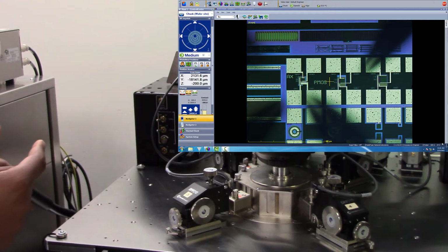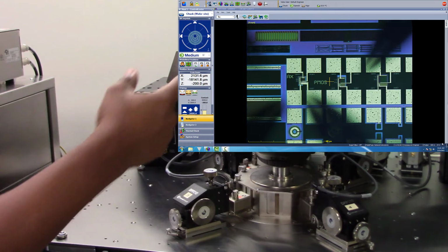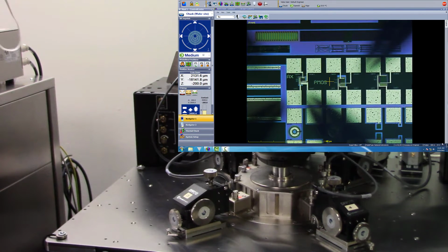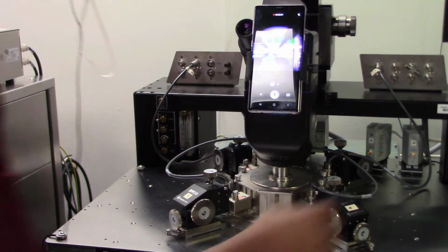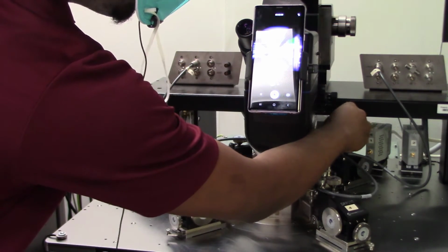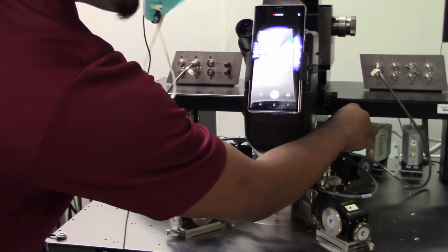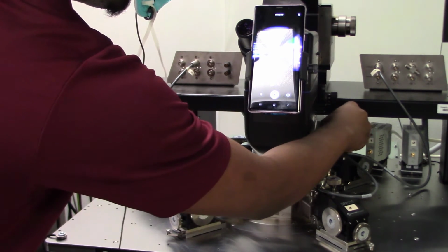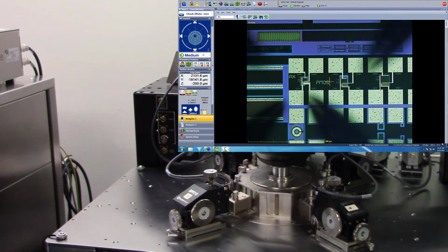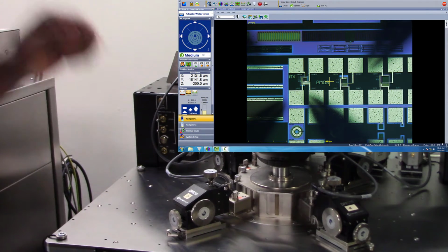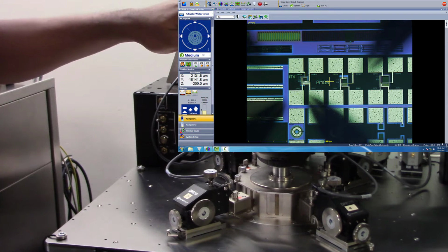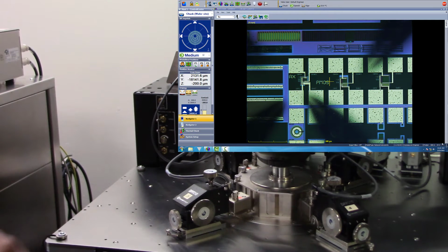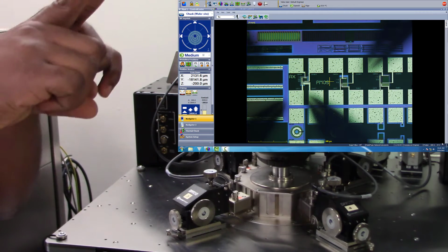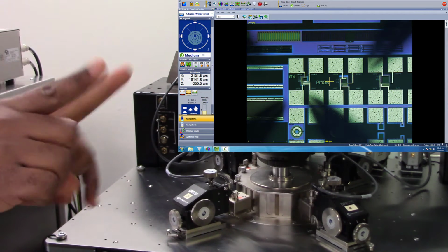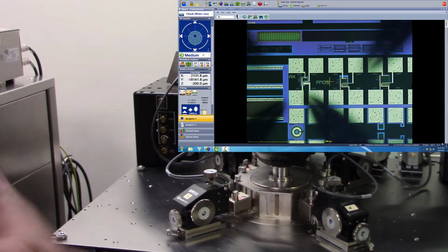So I'm going to lower this down gradually, and as you can see, the probe tips are gradually becoming sharp, and any probe tip I see becoming close to another, I'm going to rotate my Z position counterclockwise so that it opens up the tip, and I fully land my probe tip. And as you can see on the screen over here, all of our 4 probe tips look out of focus and very open, more like a fish mouth which is open.